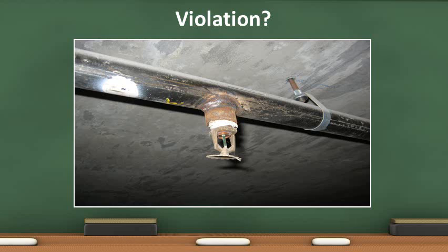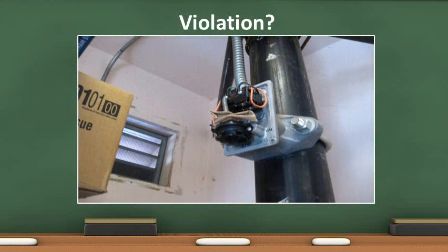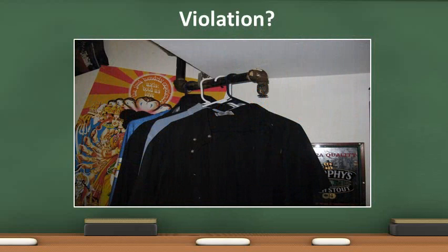What happened here? The sprinkler deflector in the photo is bent and will need to be replaced. In this photo, cardboard is wedged in the flow switch, which will keep it from sending the signal when activation of a sprinkler occurs. The flow switch cover is also missing. Sprinkler piping can't double as a closet rod. Everything attached to this system should be immediately removed.